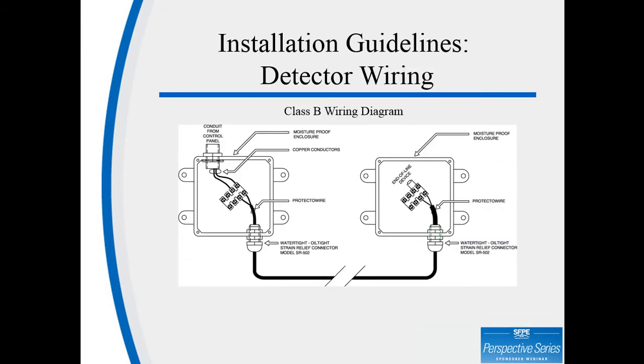This graphic shows a Class B wiring scheme, which looks very similar to the Class A with one difference. We're still coming from the control panel. We're using the interposing cable going into the junction box to the PWSC, coming out the other side of the compression fittings of the PWSC, and then through the SR502 strain relief connector, out into the field in the detection zone, and then back into the junction box. But instead of going back to the panel, we put the end-of-line resistor in to condition the circuit and monitor it.